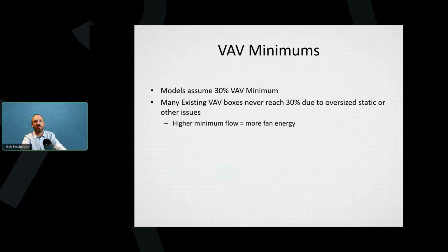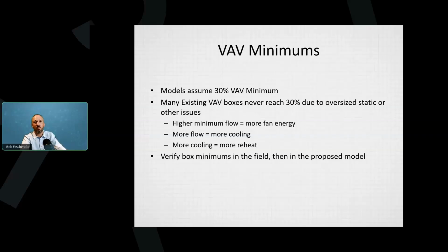Here's something that should matter to everyone, and I bet some of you are aware of this. Most models and most assumptions assume a 30% VAV minimum. If you go in the field and measure, you'll find that many boxes never reach down to the 30% minimum, because of oversized static or oversized airflow, or the box is jammed open with a screwdriver. And when the VAV box is higher than its minimum, that causes energy use in three different ways. So it's a huge option for a performance contractor to come in and fix, but you have to get it right. Higher flow means more fan energy, obviously. More flow goes through a cooling coil first, so it's more cooling. And since it's more cooling, and most of the time we're at part load, there's more reheat.